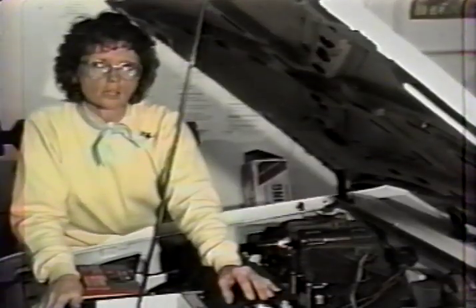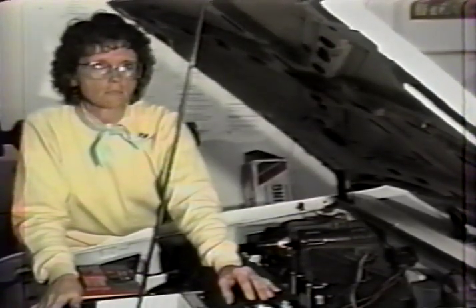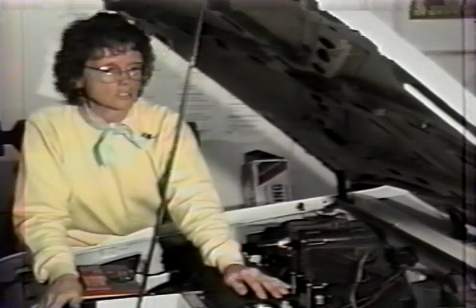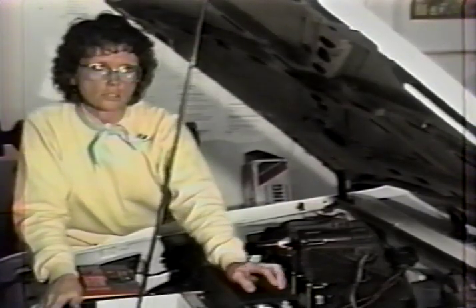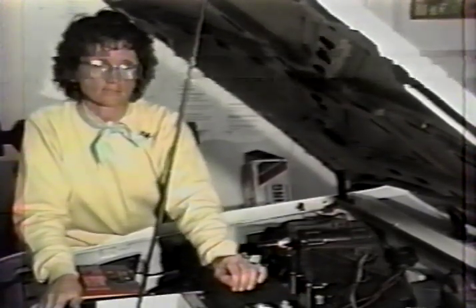Now, in the next test we're going to do, Mike refers to using the main contactor, but we have two contactors, so what we're going to do is have Rich turn on the key and close the key contactor, and then we'll use the throttle contactor in this test. Okay, Rich, turn the key. That contactor's closed. We'll hook the meter up to the controller.